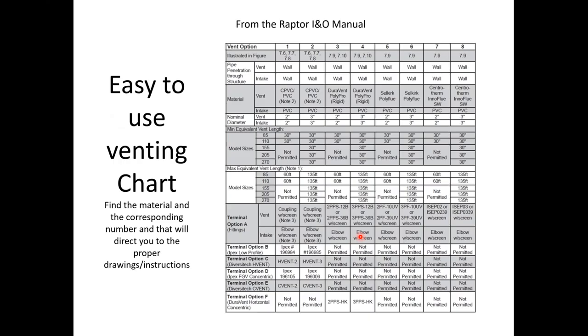So our I&O manual, this is from the Raptor's I&O manual. Our venting tables can be very thick. I think it's almost 70 pages of venting. You don't need to read all 70 pages. This is showing our sidewall. If you're venting a CPVC and you're venting a 2-inch, we need to pay attention to these 3 figures. Don't need to read all 70 pages. Just glance over these, basically over 3 pages, and it'll show you how you can vent them. If you're using Duravent or Centrotherm or any of the polypropylene manufacturers, that would be the pages that you would follow.